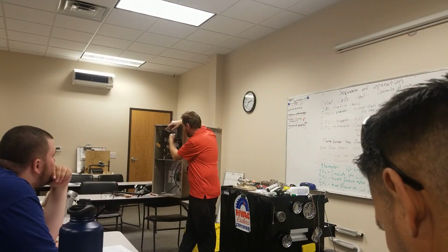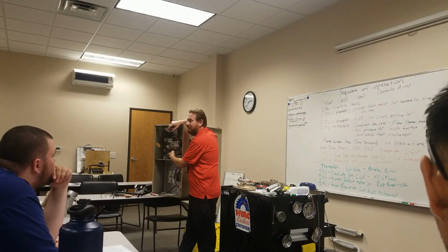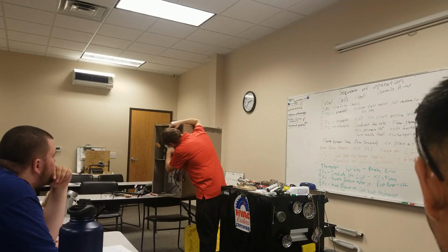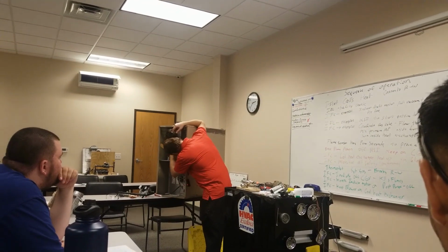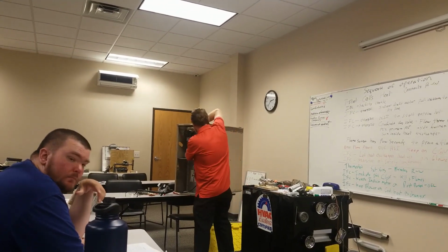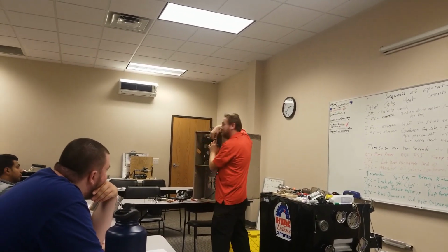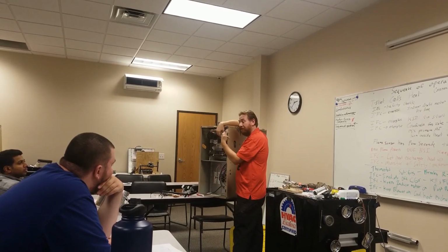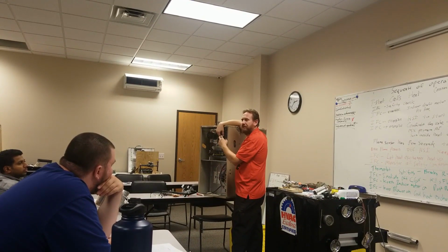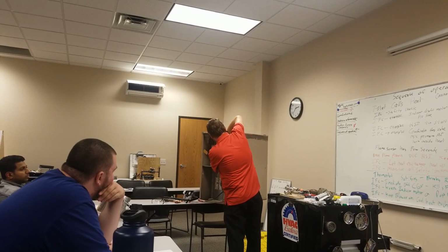So what's between that? There's the pressure switch and the igniter. So I can also unplug my igniter. Here's the plug for it. I just unplug it. See if I'm getting voltage there to it. Wait for the correct sequence. Oh, I never got voltage here. Well, let me check my pressure switch.